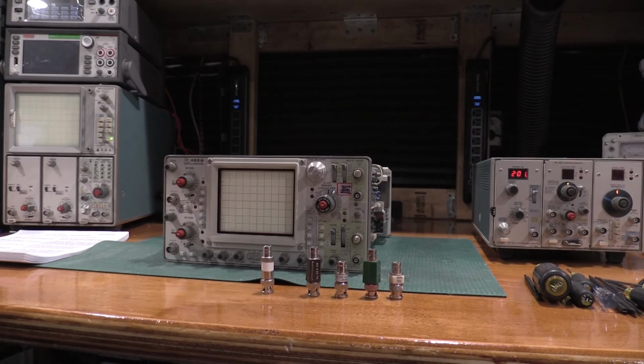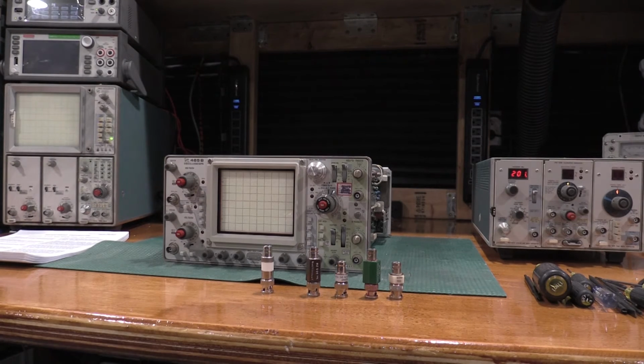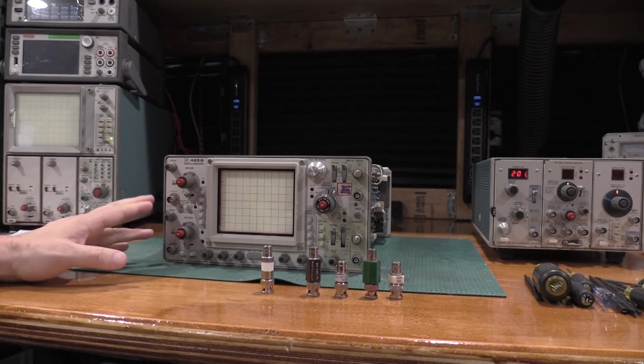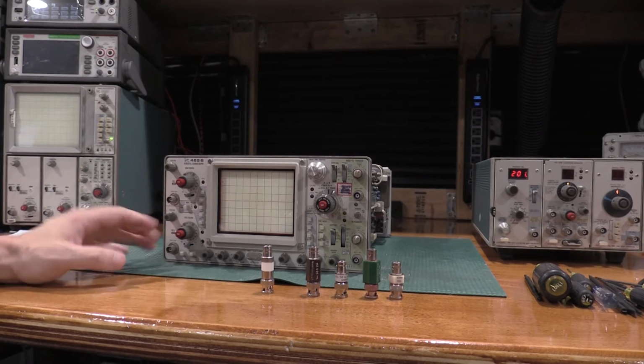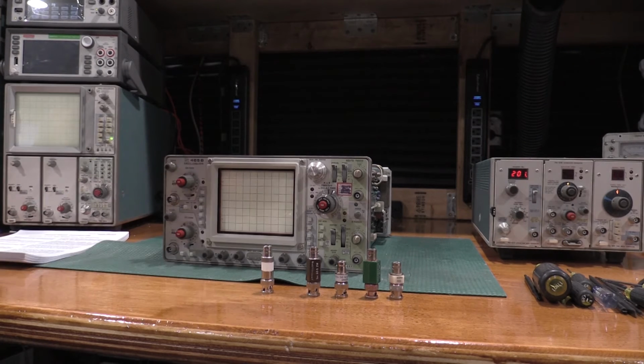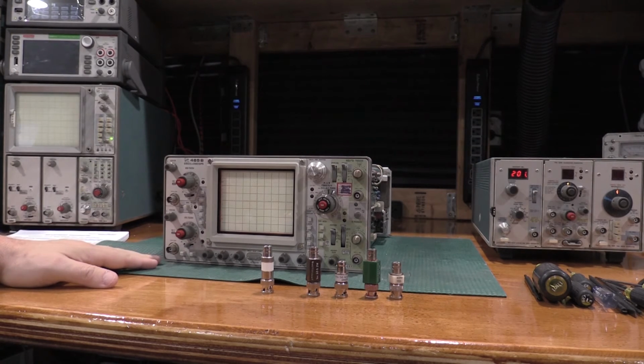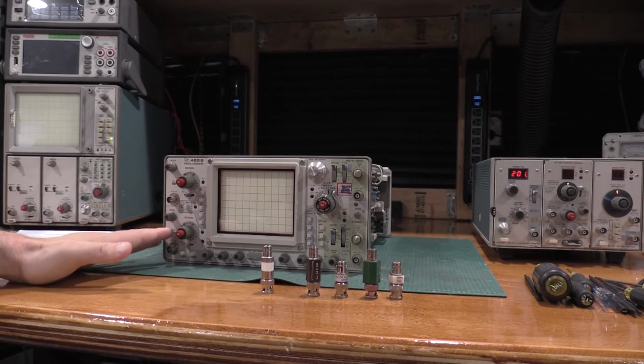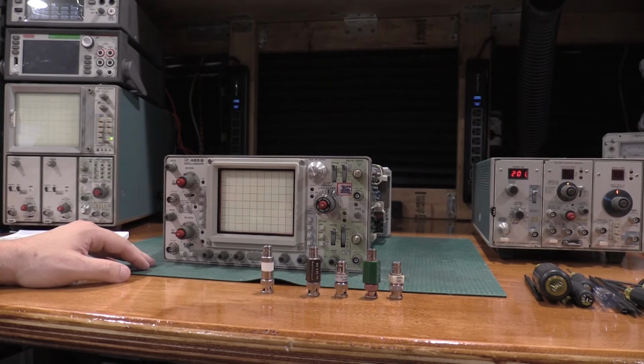power supply. There is one piece of gear that I don't have for this scope, and that is a CT3. I'm looking for one, but I don't have one yet. From reading the calibration procedure, what that does is it puts an incredibly low-level signal into the scope so we can set the trigger points. That being the case, I do have a piece of gear that's going to sub in for that, my HP 8657A RF signal generator. I need 10 megahertz at about 20 millivolts. Right in the wheelhouse of the HP, so I got him warming up as well.